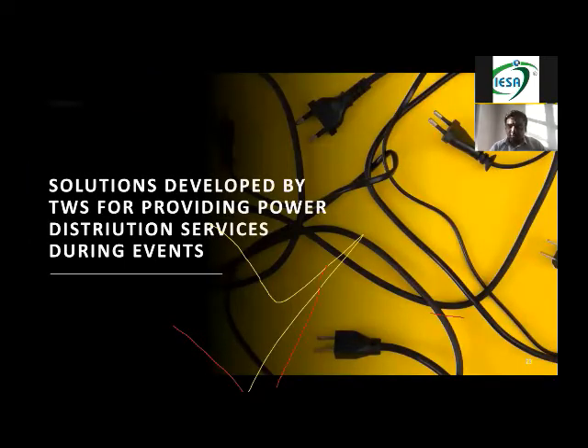Okay. So again, just to recap, what can go wrong? The right equipment which is available in the market: the sockets, the power locks, the MCB. Now everything has to come together and form a panel or a junction box. For every power distribution company, the only things available in the market are the power locks you can buy, the right size of wires you can buy, the sockets you can buy, and the MCBs you can buy. Now the whole structure of your panel also has to be IP. I told you that your sockets are IP65, your power locks can be IP67, but your panel enclosure also has to be enclosed so that the water doesn't go in, because most of the time these panels are placed outside.